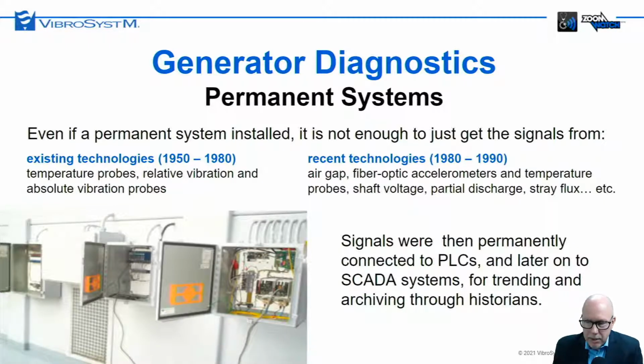So we had existing technologies, let's say technologies that were invented from the 50s to the 80s. We're talking about temperature probes, relative vibration probes, absolute vibration probes, and then on to more recent technologies like equipment that was designed in the 80s and 90s. We're talking about air gap sensors, fiber optic accelerometers, or fiber optic temperature probes, shaft voltage monitoring equipment, partial discharge monitoring equipment, stray flux, and so on.